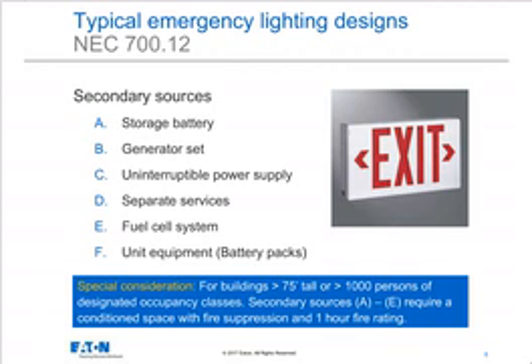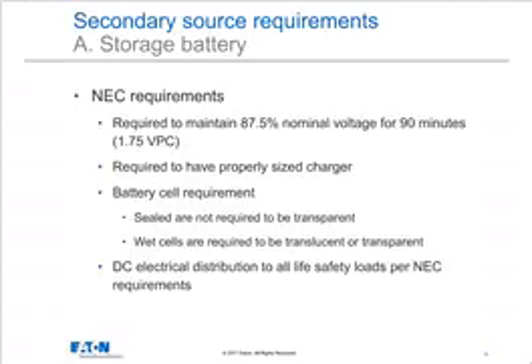So that means the walls of the room are going to have a 1-hour rating, as are the doors and any windows. And if you're familiar with these types of installations, it can add a great deal of expense to your building when you put in a room with at least a 1-hour fire rating. But that is required no matter what source you use for emergency lighting. So let's take a look at them real quickly one at a time.